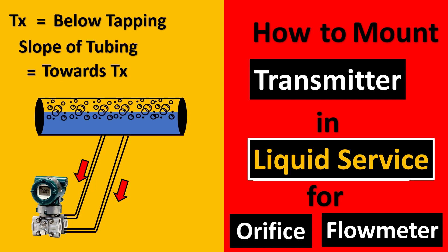Why? Because you want the liquid to be trapped here and if there is any gas which is lighter, it will always stay up and it will never come to your transmitter and thus the gas would not get trapped inside your impulse lines.